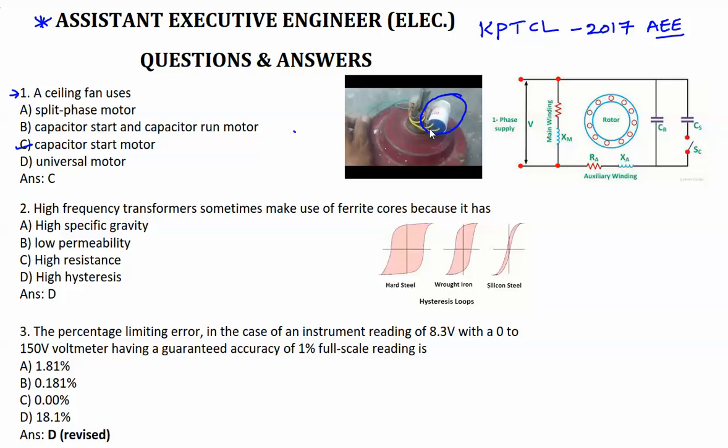Now you can ask where we'll use capacitor start and capacitor run motors. As you can see in this diagram, we have auxiliary winding and main winding. Here we have two capacitances - one is for running condition, second one is for starting condition. In case of capacitor start motors, there is no capacitor for running conditions. For power factor improvement, we will use running capacitors.